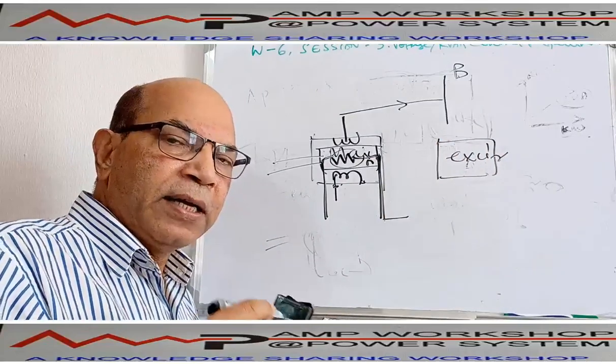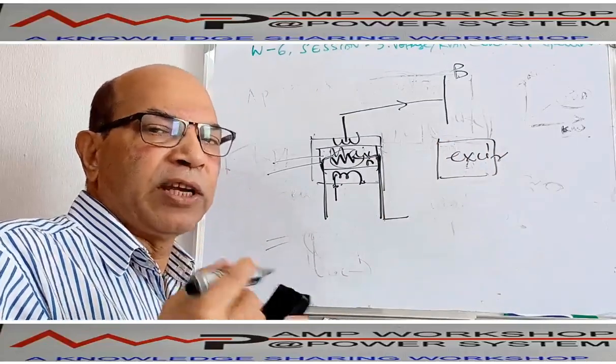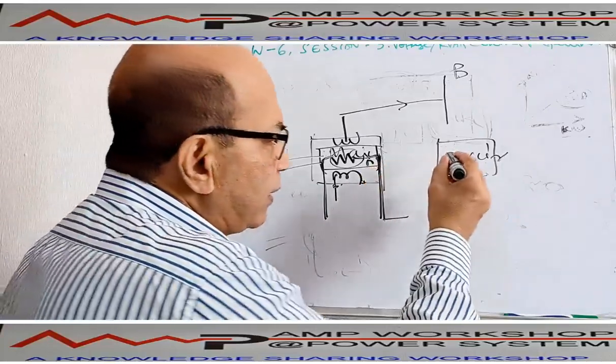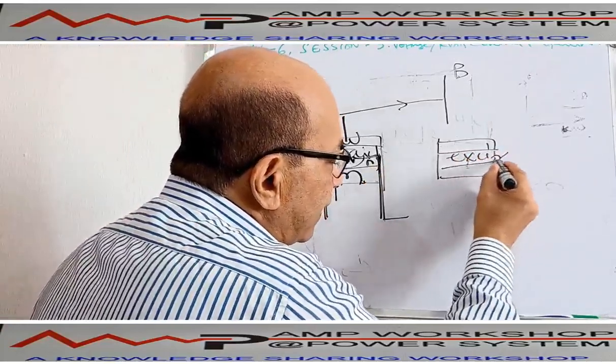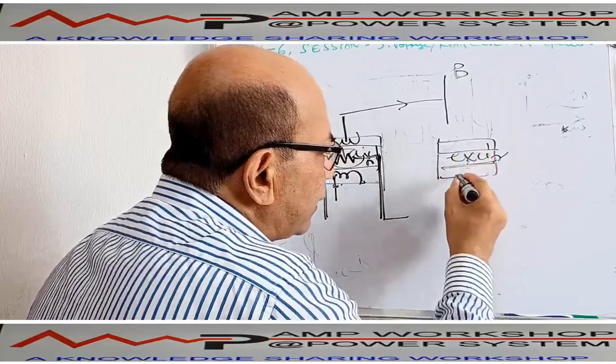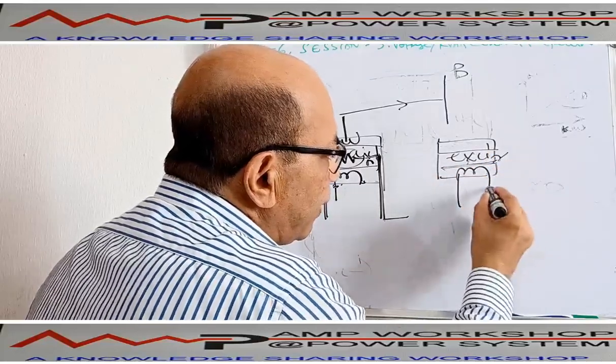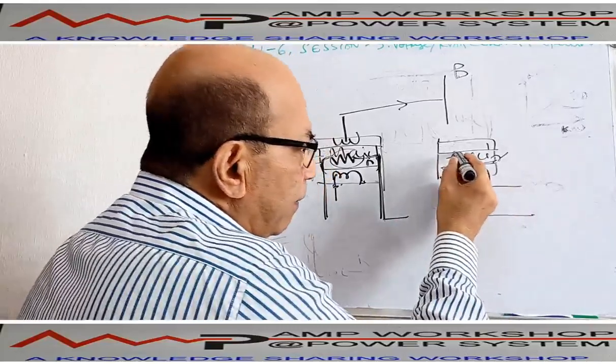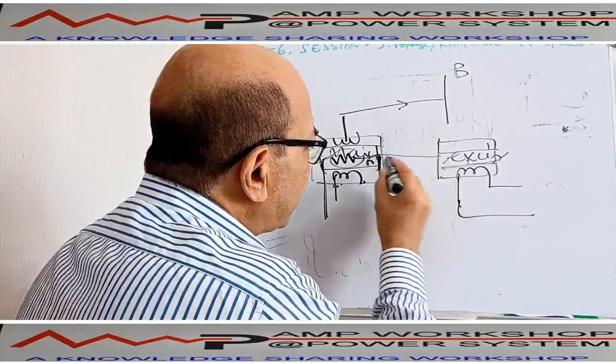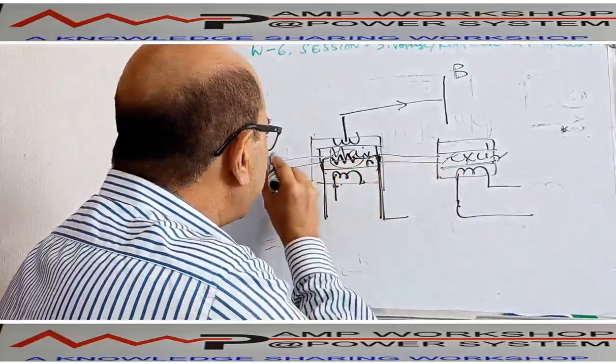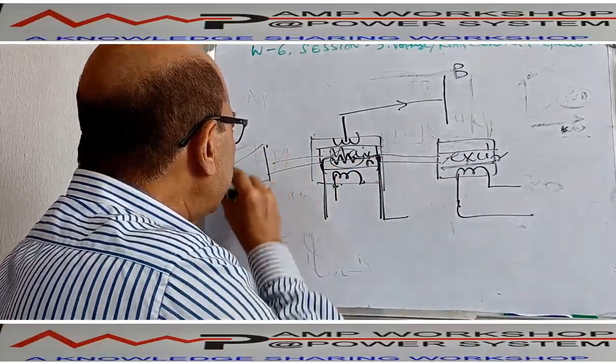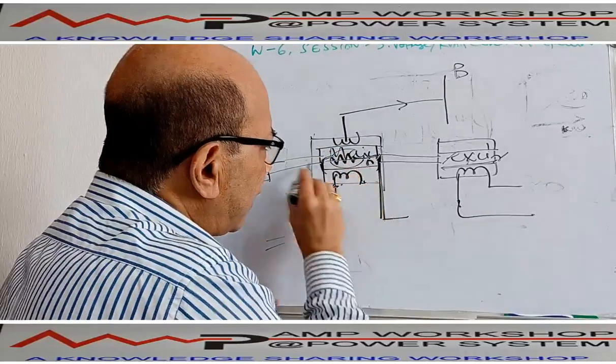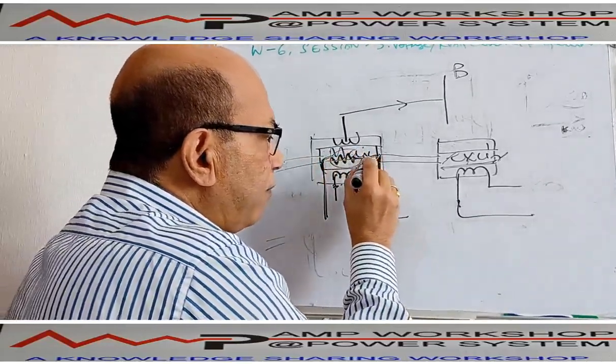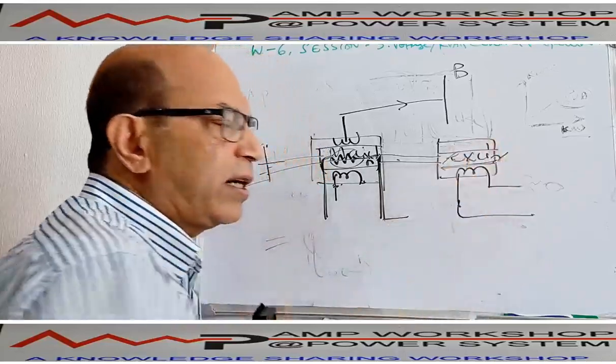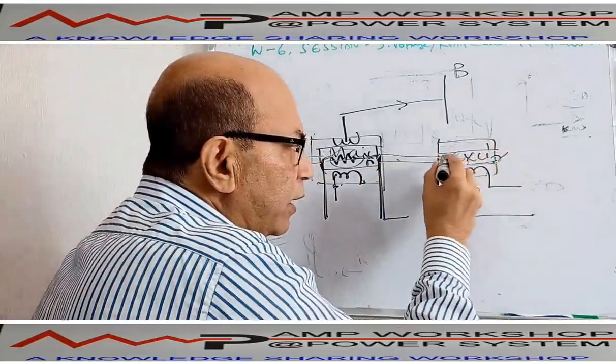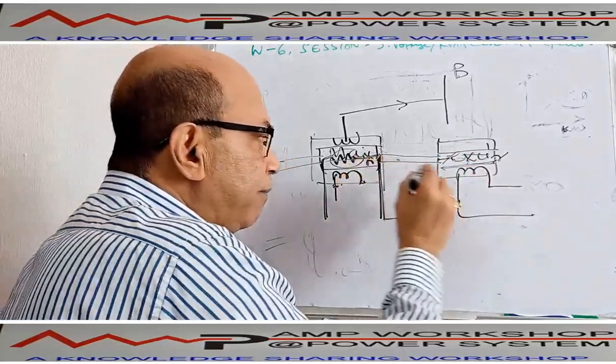Exciter, what is happening? The field winding is fixed, the field winding is not rotating. That means the armature or stator is rotating here, and the field winding is fixed, but this is coupled with the rotor shaft, the main machine rotor. The turbine shaft is coupled with the main generator rotor, and the main generator rotor is coupled with the exciter stator or armature. So the exciter is rotating here, and the field is not rotating.